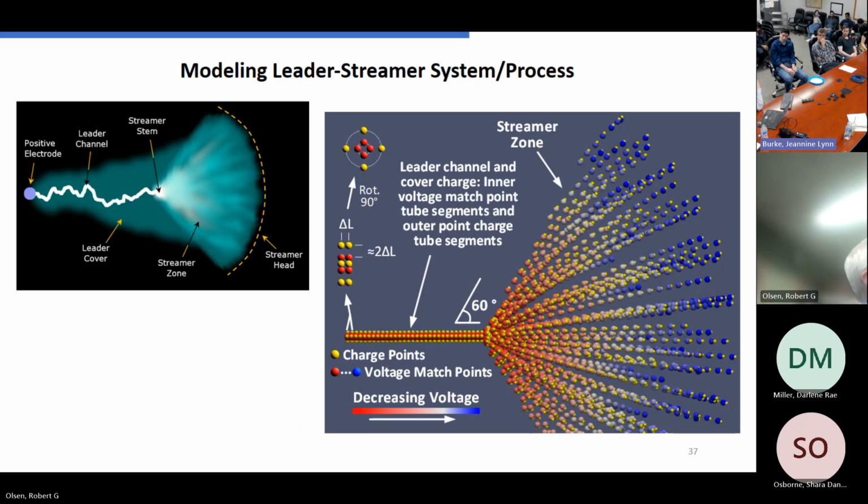When they're thermally limited, they're doing a lot of, what's the word I'm looking for? DLR. It's basically measuring weather parameters. I can't remember what it is right now, I'm blanking on it. Basically you set ratings on the lines, dynamic line rating. That's one of the things being used a lot, based on weather variables.